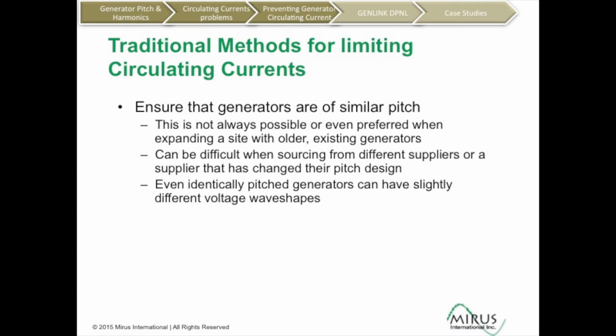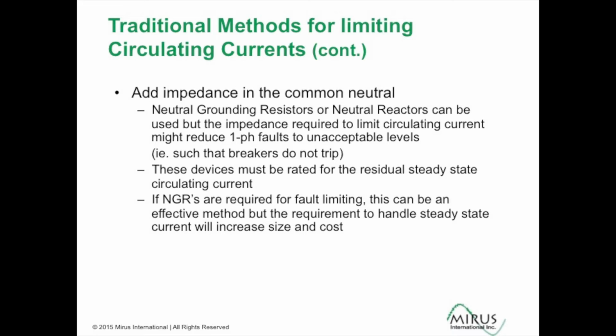So if we can put exactly the same generators in with the same pitch, then that will reduce the possibility of circulating currents. But even identically pitched generators can have slightly different wave shapes, which can still result in some circulating current. Or we can add impedance in the common neutral. Neutral grounding resistors often are used to limit fault level in generator applications. We can have high resistance grounded systems, or we can have low resistance grounded systems. Those resistors will introduce impedance and will limit that circulating current.